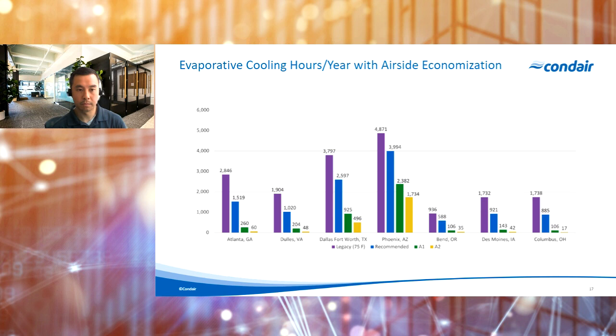To examine air side economization some more, we can look at the number of hours per year an evaporative cooling system would have to operate to maintain different operating envelopes. What we're looking at here is what we call a legacy, definitely colder temperature, the recommended envelope, and then also two of the allowables. Outside of the hottest regions in the United States, places like Texas and Phoenix, a direct evaporative cooling system would only have to run about 1,500 hours or less when cooling to the recommended temperature envelope. Though if that same facility was allowed to utilize the allowable envelopes, these hours drop pretty substantially.